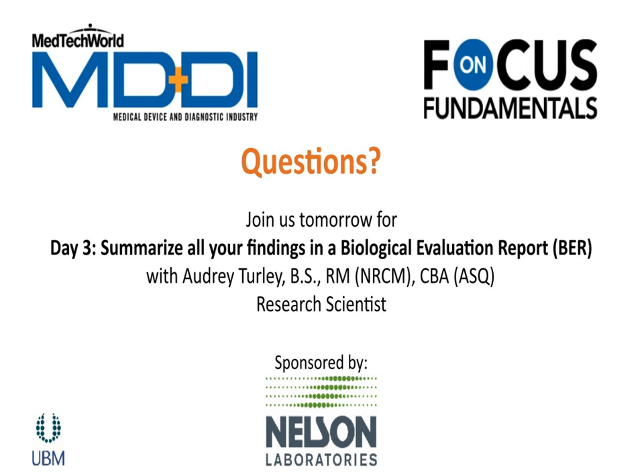Yeah, so I also read this, and I think it may be very, very difficult. Trying to identify a novel compound that may cause genotoxicity is near impossible. The studies that you would need to reference, the proof that you would need, may not exist. Now, if you have a very common genotoxin that is released and easily identified in typical approaches for E&L, then you should be okay. You can identify that amount, get the quantitative response from the instrument, and determine whether you have a risk posed to the patient who is going to be exposed to that particular chemical with typical use of the device.